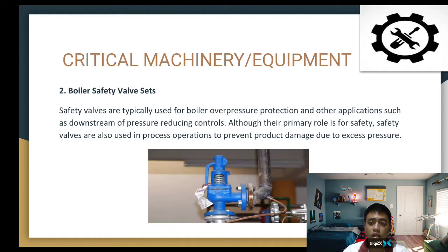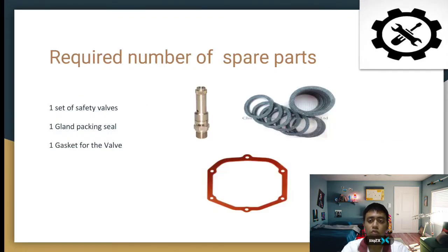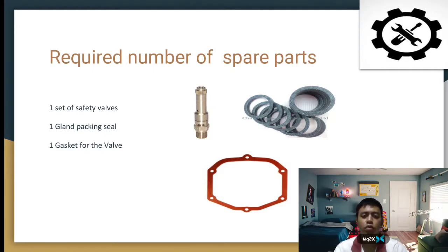These safety valves are just like relief valves, but the difference between the two is that the safety valve uses air pressure and it can exhaust in the atmospheric area. The relief valve is also a safety valve, but the flow of it is liquid, so that the exhaust of the liquid can go back to its system. That is the difference of the two. The required number of spare parts of these boiler safety valve sets are one set of safety valves, one gland packing seal, and one gasket for the valve. The next reporter will be Navarro Robert Jan.